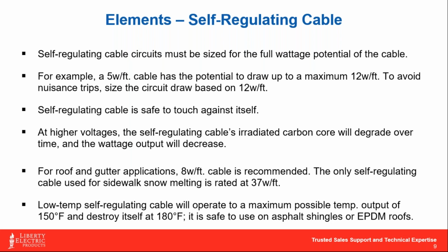But to give you some context, a low temp self-regulating cable only works to a maximum of 150 degree output F. Okay, so it is safe to use on things like PVC pipes or asphalt shingle roofs or EPDM roofs. We don't get hot enough to where that cable is going to embed itself into the material. So that makes it an incredibly popular choice for, say, roof and gutter application. Those are some of the reasons why you'll see self-reg cable, especially in the commercial roof and gutter segment, is probably about 99% of the product used for that particular application.